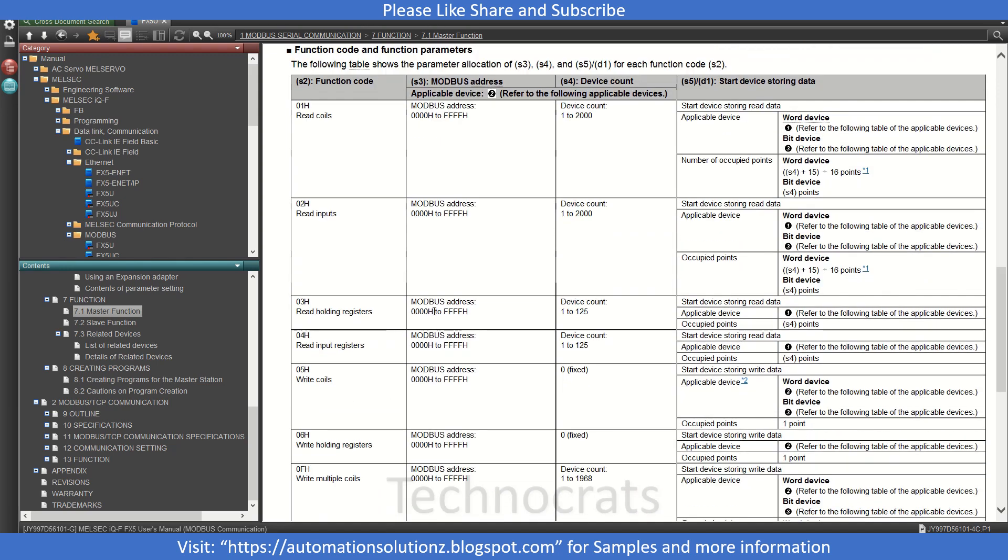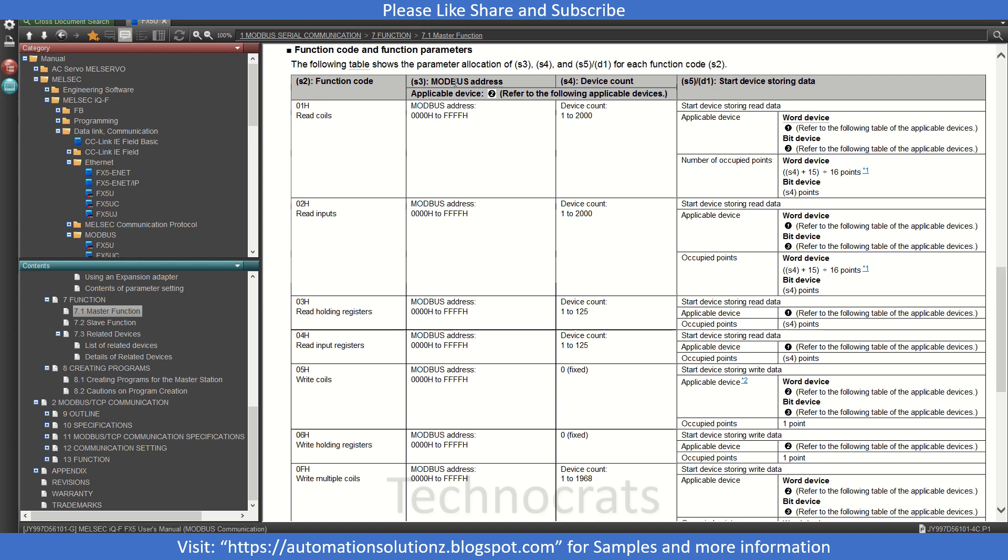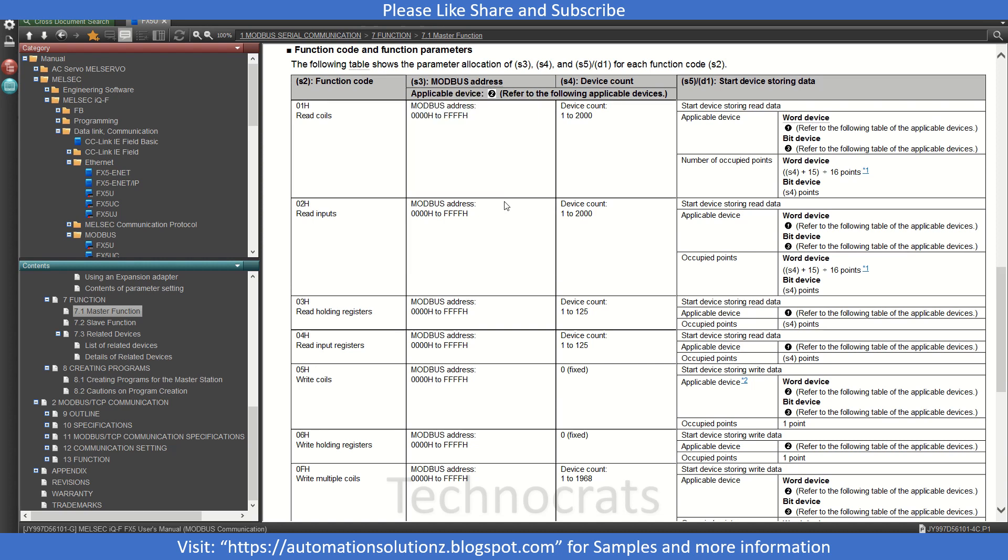Now S3 is your Modbus address. It will go from 0 to 4 times F, that is your maximum value. And here we have S4, that is device count. And S5 is your starting device storage data address, that can be D100 to 200 or anything else.